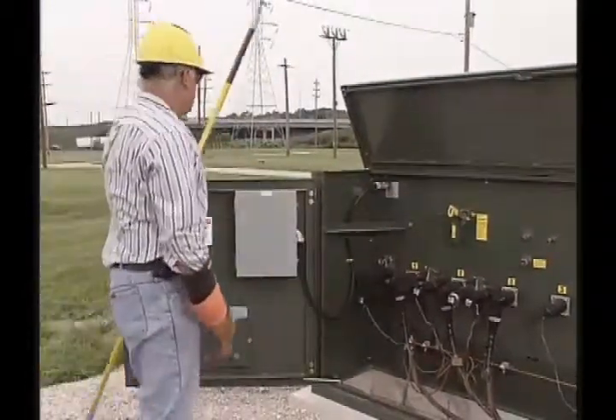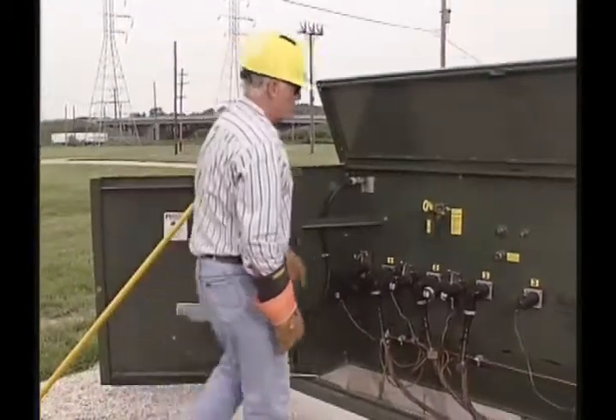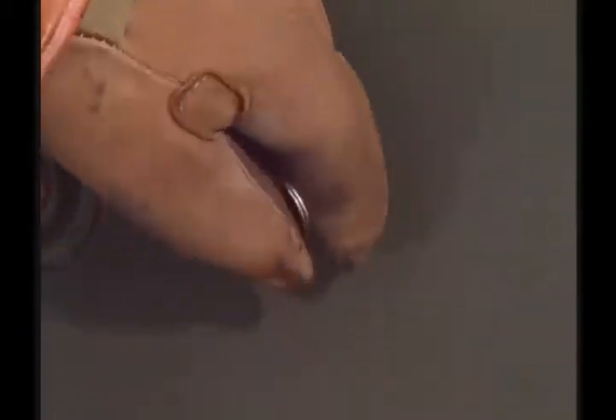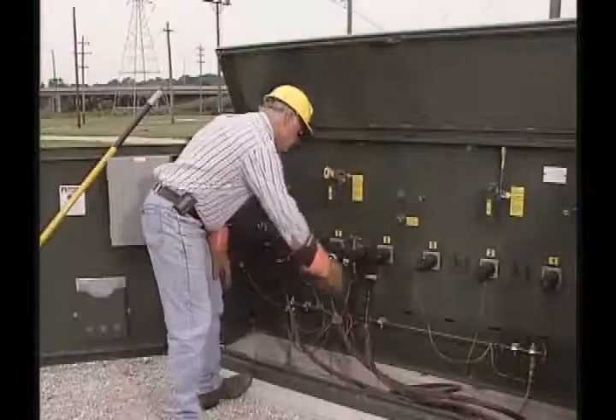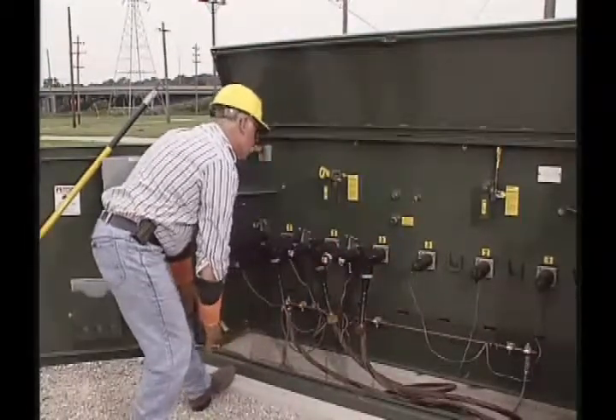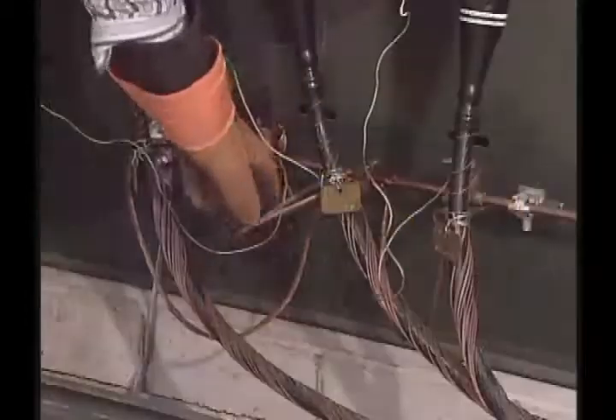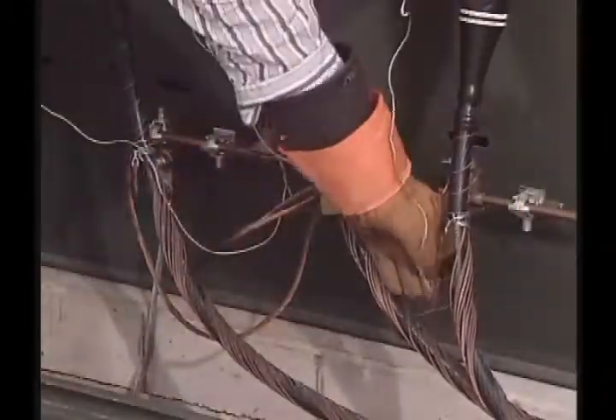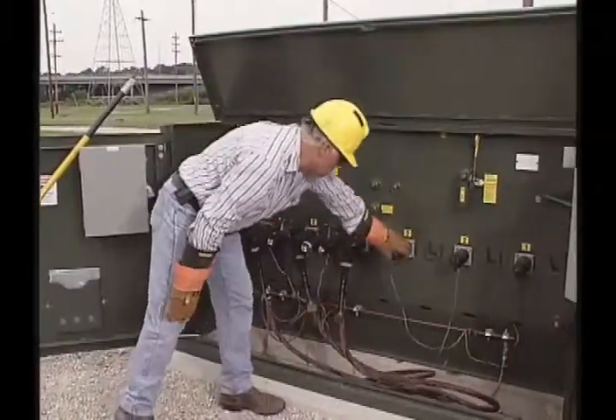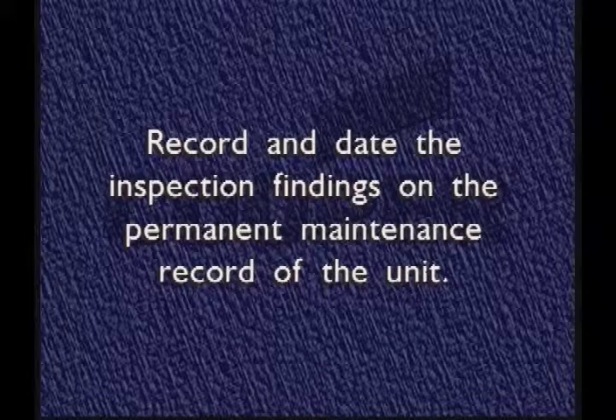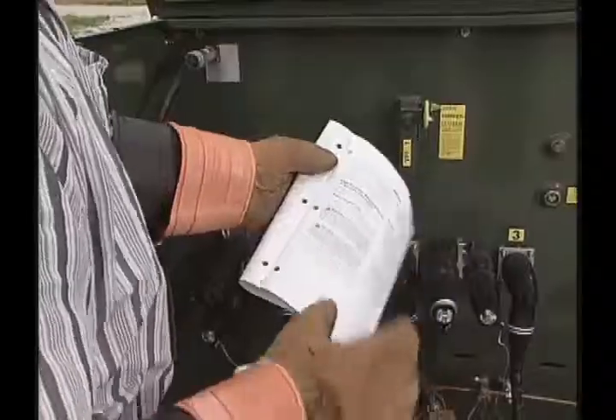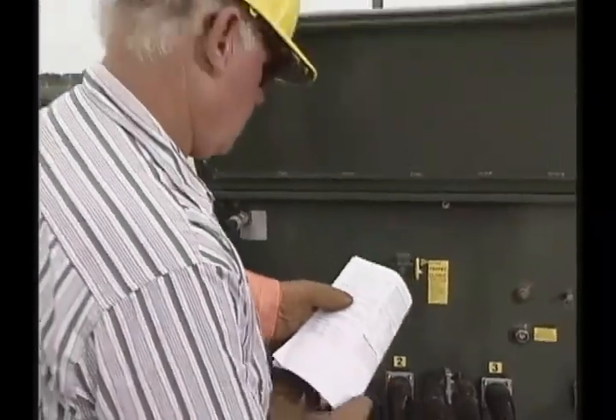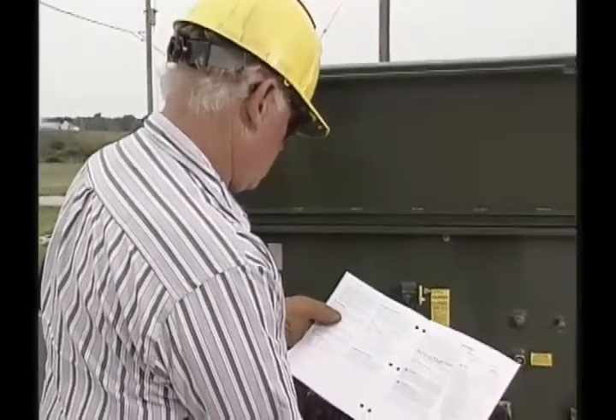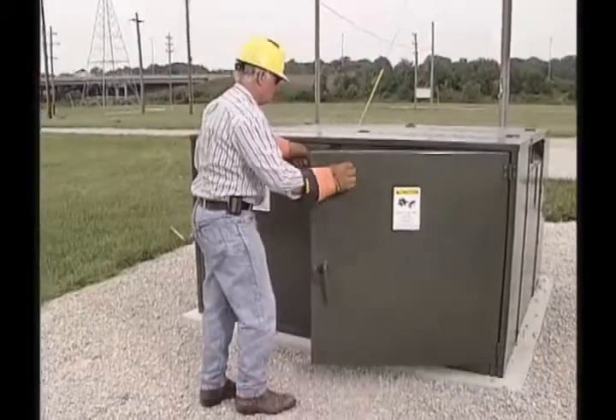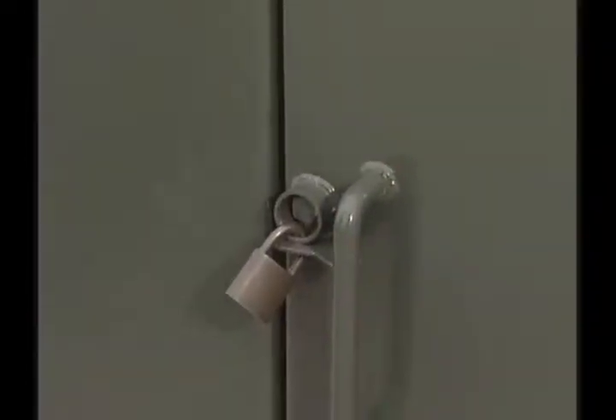First, de-energize, ground, and remove the switchgear from service. Then reduce the internal tank pressure and check the oil level. Next, inspect the unit for unusual wear to the paint finish and damage to the bushings and elbows. Make sure all connections are secure. Check for oil leaks and any other abnormal indications of wear or abuse. Record and date the inspection findings on the permanent maintenance record of the unit. For detailed maintenance, inspection, and oil testing information, refer to the VFI service manual. Lastly, make sure that the cabinet doors lock securely.